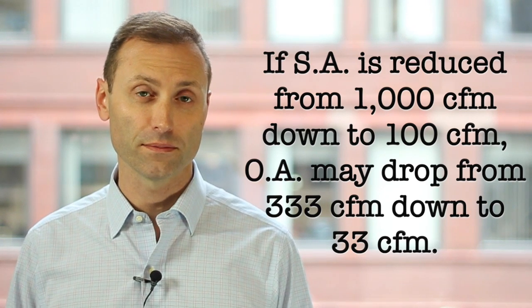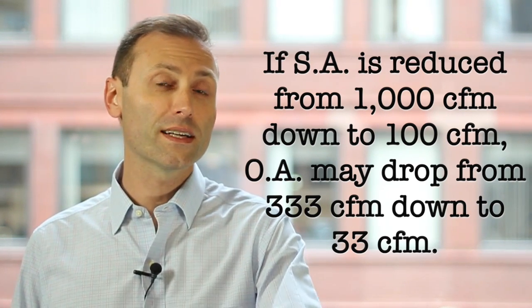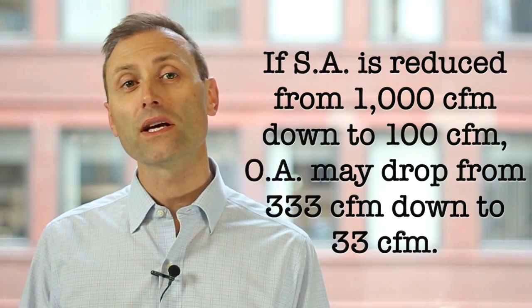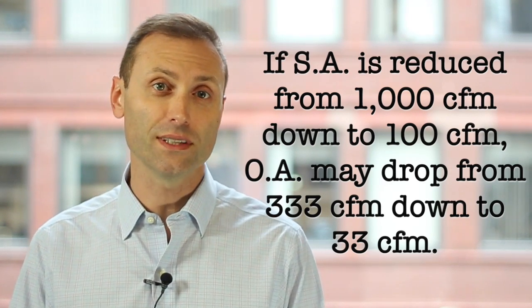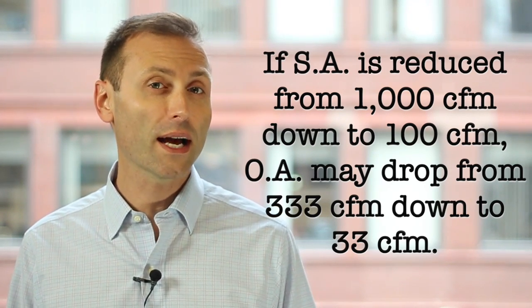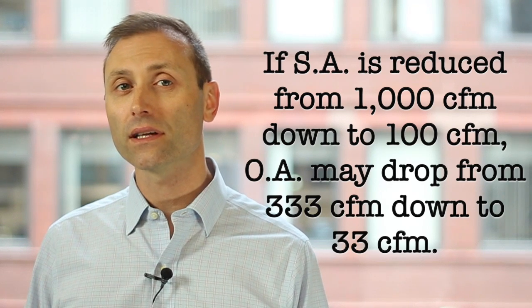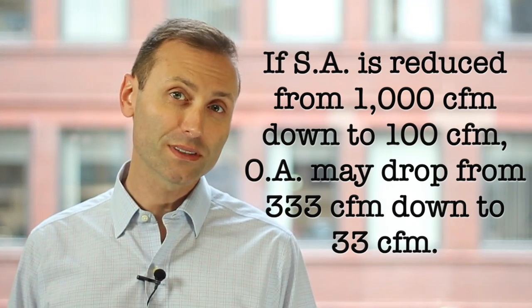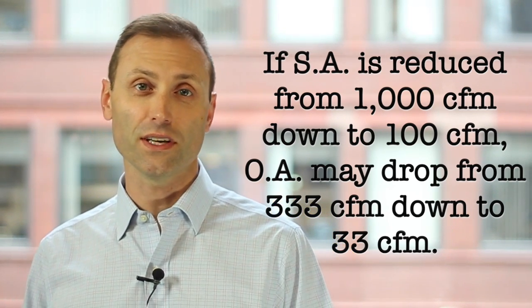But what happens if people start to get cold? The VAV system may no longer supply a total of 1,000 CFM to the space. It may reduce the airflow down to a total of 100 CFM. Well, if the outdoor air is provided as a fixed percent, the space will now only get 33 CFM. So, did you see what happened? Our outdoor air ventilation went from 333 CFM down to 33 CFM.